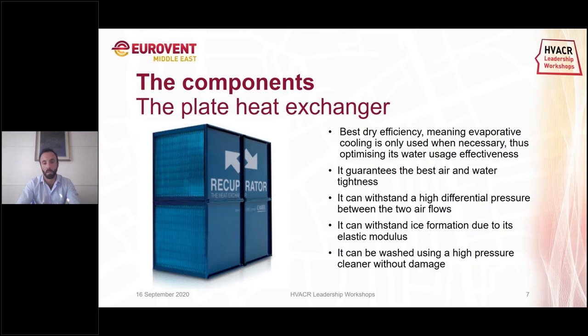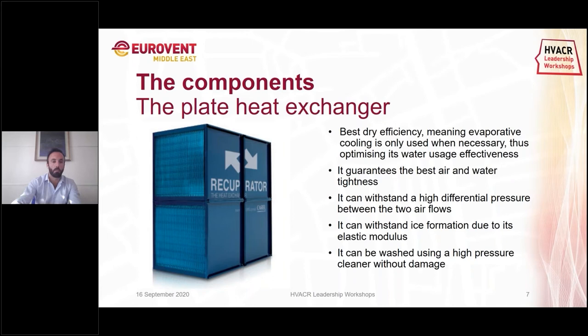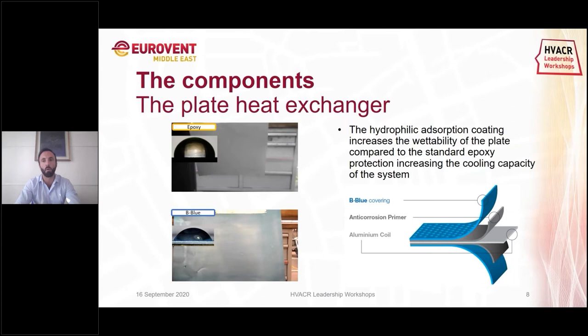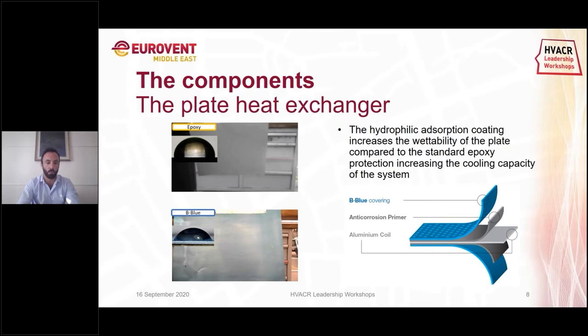The solution is resistant to ice formation, and it can withstand high differential pressure because it is composed of aluminium. One main point of the plate heat exchanger is that humidification at the inlet of the heat exchanger and also inside it keeps the temperature of the airflow close to the saturation curve, so we are working a lot with the wet bulb temperature of the airflow being humidified.